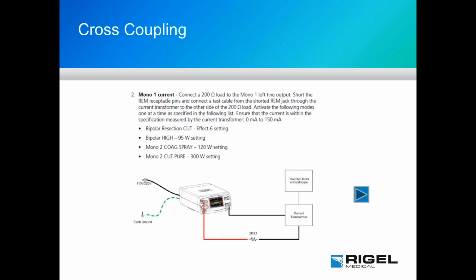So the next thing we're going to do is what's called cross-coupling. A number of different manufacturers will have you do this test. They may call it different things. The concept behind the test is, since we have monopolar outputs and bipolar outputs, we can have leads or surgical tools in a procedure attached to monopolar 1, for instance, and also perhaps have a bipolar tool attached to the patient somewhere as well, or perhaps leaning close to the patient.